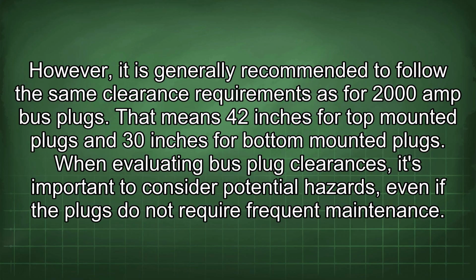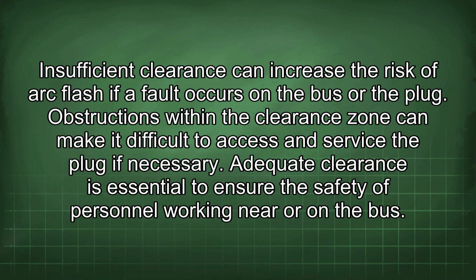When evaluating bus plug clearances, it's important to consider potential hazards, even if the plugs do not require frequent maintenance. Insufficient clearance can increase the risk of arc flash if a fault occurs on the bus or the plug. Obstructions within the clearance zone can make it difficult to access and service the plug if necessary. Adequate clearance is essential to ensure the safety of personnel working near or on the bus.